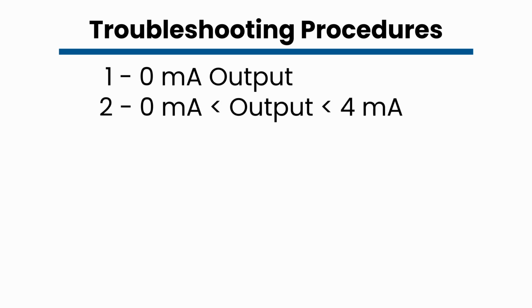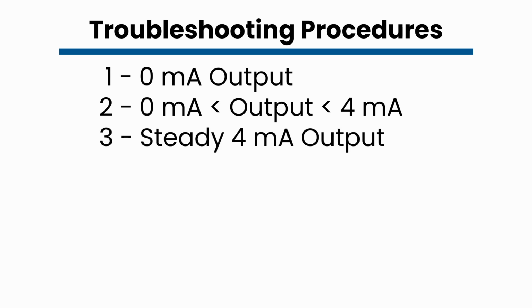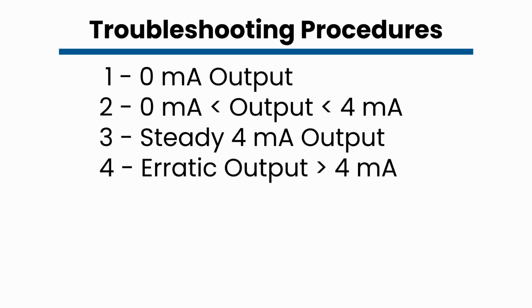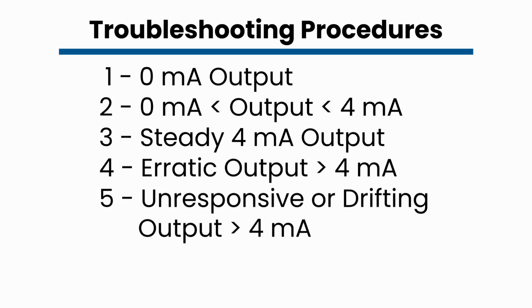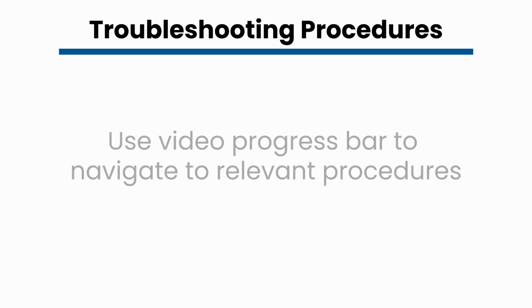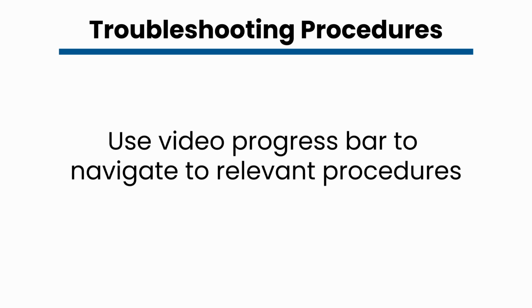They are broken down as follows. Number 1 is no output. Number 2 is an output greater than 0 and less than 4 milliamps. Number 3 is a steady 4 milliamp output. Number 4 is an erratic output above 4 milliamps. And number 5 is an unresponsive or drifting output above 4 milliamps. Please use the progress bar at the bottom of this video to scroll to whichever symptoms are occurring with your sensor.